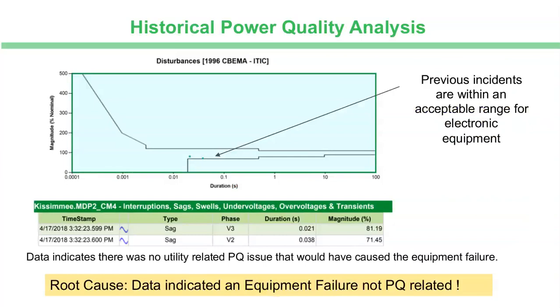And so the other very important thing that the power quality meters do is they track power quality over time. And what I'm showing you is a standard kind of plot for power quality. It's based upon what's known as CBEMA, which stands for Computer and Business Equipment Manufacturers Association. And in a CBEMA curve, what you're looking at are these events. Each event is plotted based upon the magnitude, where 100% is nominal, and you can see 100% is right in the middle of this envelope. So you have magnitude, 100, 200, 300, 400, 500%. And then on the horizontal axis, you have time.